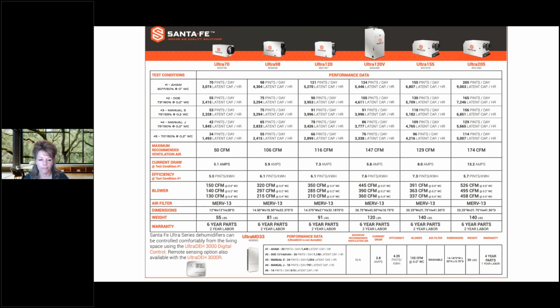And just because we know a lot of homeowners like their master bedrooms much cooler, we did put in the 70 degrees and 50% relative humidity as well. And it shows you, obviously, as the temperature is lower, a 70-pint dehumidifier is only 70 pints at 80 degrees, 60% relative humidity. As the temperature is lower, and the RH lowers, then the capacities become less. And that's all dehumidifiers. We are sharing this performance data because we feel that it's very important to the industry to understand this when applying a dehumidifier, to make sure you're getting as much dehumidification as you need.